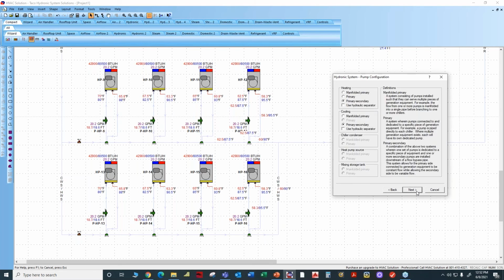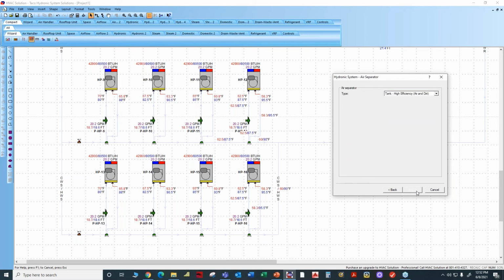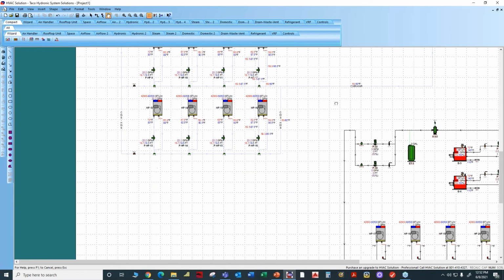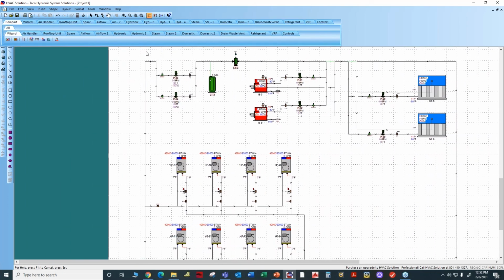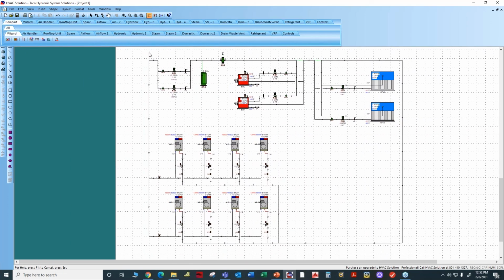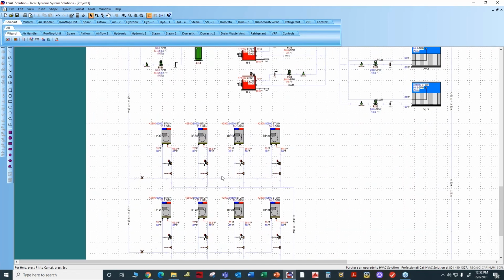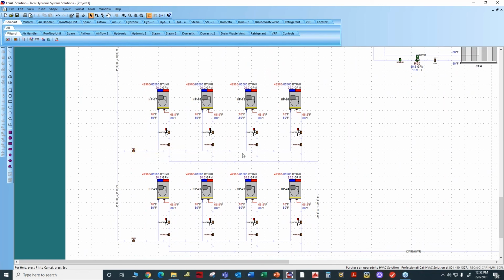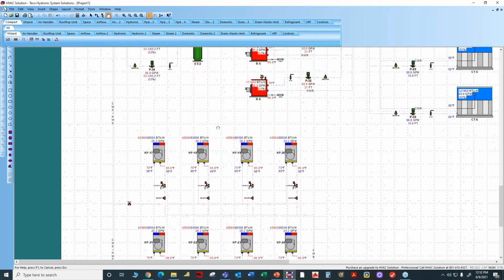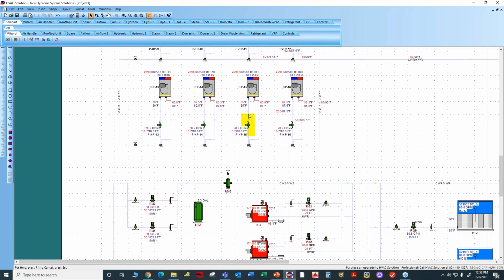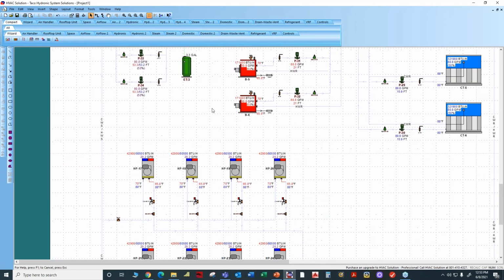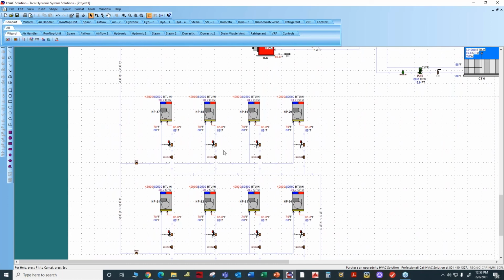The magic of the HSS software, the amazing software. We're going to look at a conventional system using pumps as the main circulators and two-way control valves, similar to what we just talked about. So in this case, we have two pipes: a supply pipe here and a return pipe on each floor. And then for the branch piping that goes out, we have a two-way control valve, which adds system resistance, which is why the circulator, load match or single pipe system uses less energy, because there's no control valve to overcome the resistance. There's just the heat exchanger inside the heat pump, but there's no control valve.